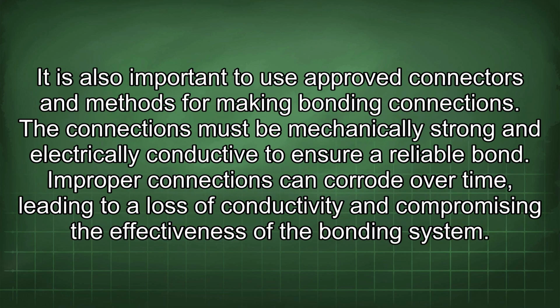It is also important to use approved connectors and methods for making bonding connections. The connections must be mechanically strong and electrically conductive to ensure a reliable bond. Improper connections can corrode over time, leading to a loss of conductivity and compromising the effectiveness of the bonding system.